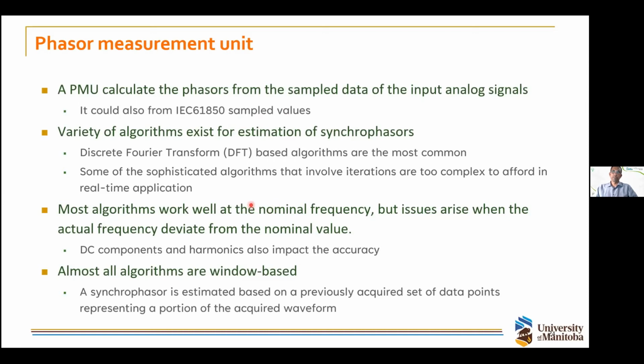For phasor estimation, there are many algorithms. Mostly they use the discrete Fourier transform, and there are also some other, let's say, optimization-based algorithms. Some of them are very complex, maybe difficult to implement in real time, depending on your resources. The problem is that many algorithms work very well at the nominal frequency, but problems arise when the frequency of the actual measured signal changes. And you can also have errors because the actual signals can have noise and harmonics, and especially the currents can have DC offset values, and these also introduce some errors into your measurements.